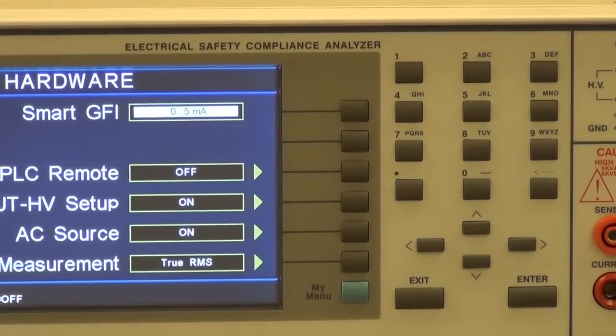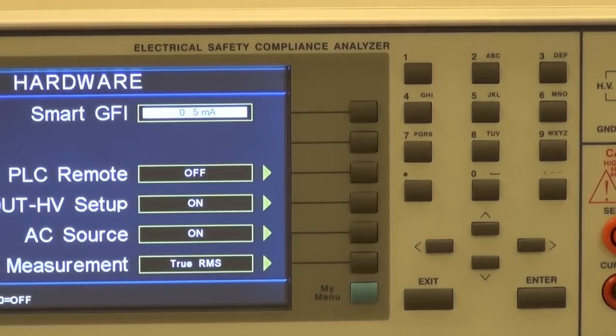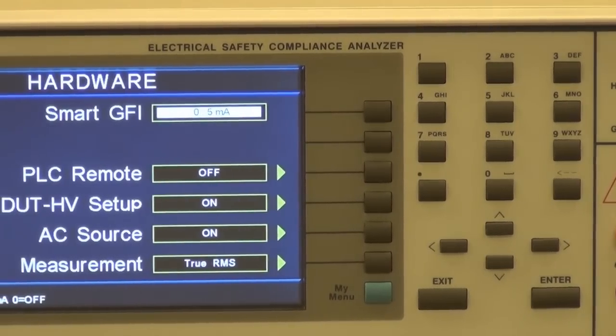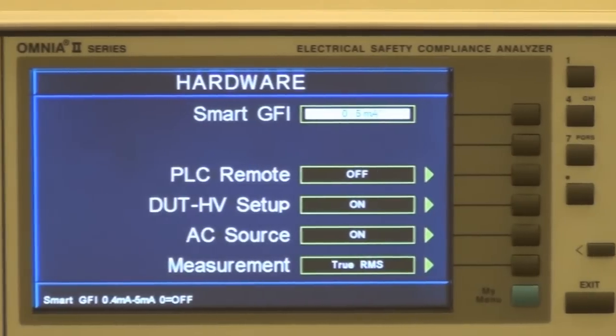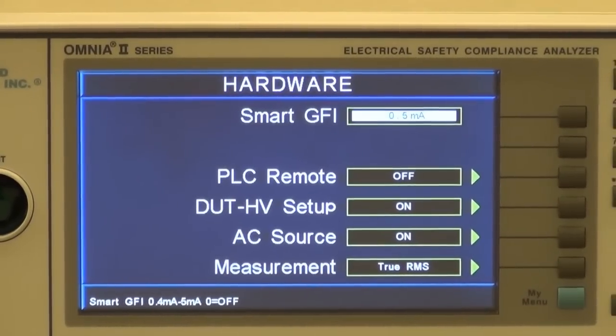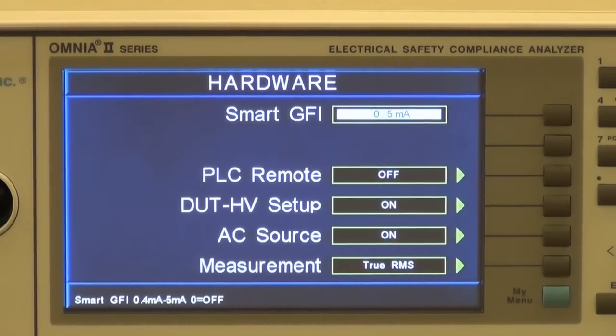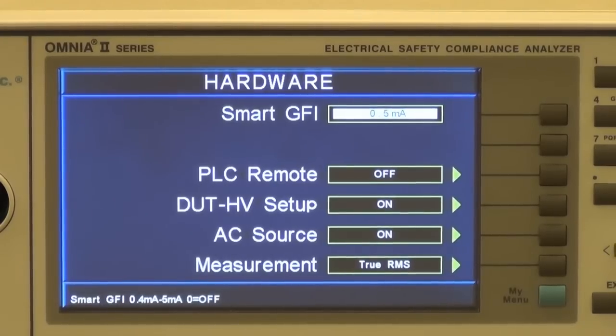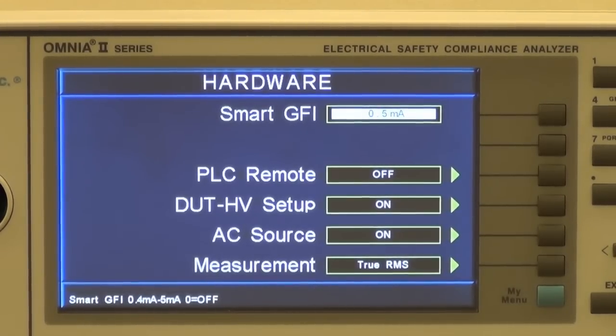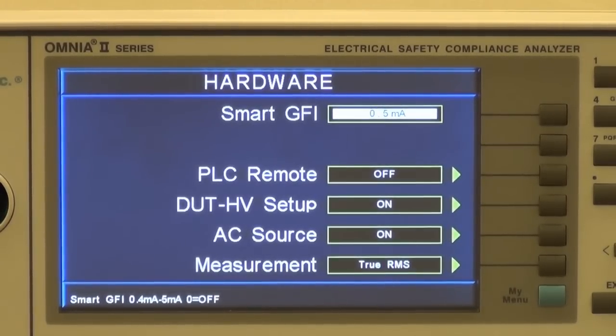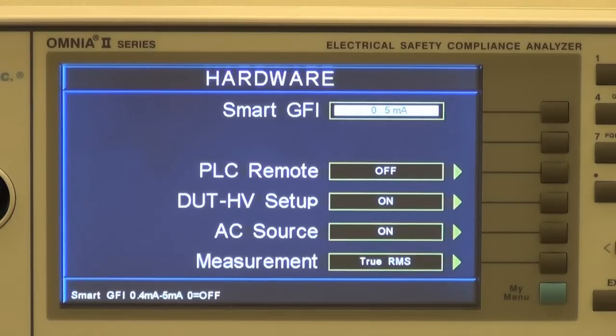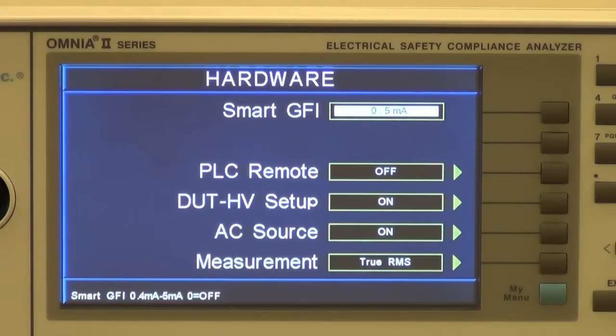The Smart GFI can be set to 0 for off, or adjusted from 400 microamps all the way up to 5 milliamps. Setting the GFI to 0 will only disable the ground current failure detectors. It does not disable the capability to externally earth-ground the return lead. The PLC remote setting allows the user to operate the Omnia in a remote mode using the remote I/O on the rear panel of the instrument.